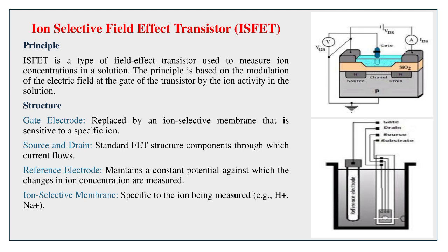Ion-Selective Field Effect Transistor (ISFET) — Principle. ISFET is a type of field effect transistor used to measure ion concentrations in a solution. The principle is based on the modulation of the electric field at the gate of the transistor by the ion activity in the solution.